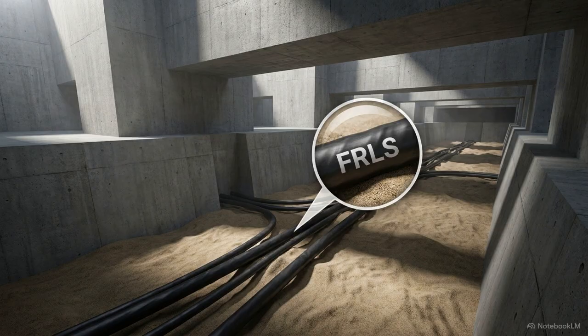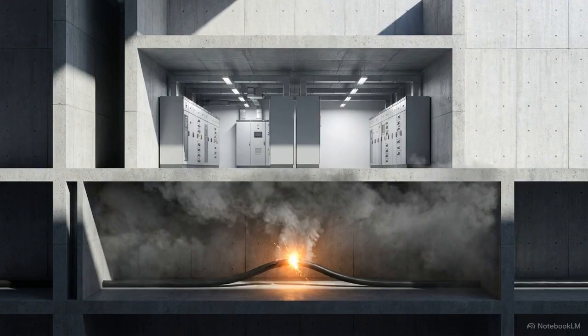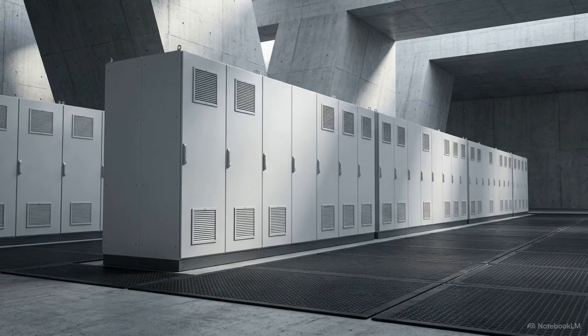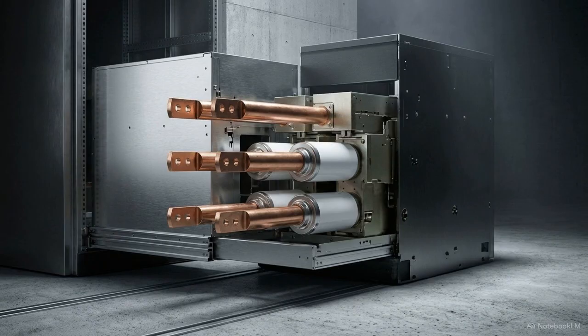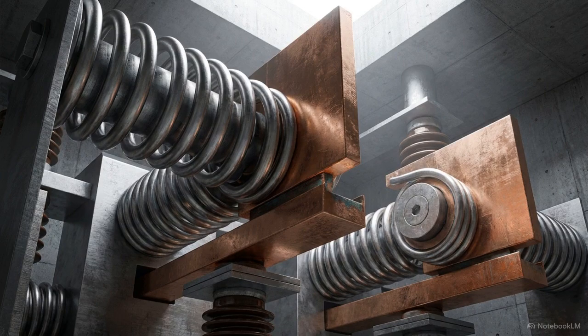Moving from the transformer yard into the underground cable trenches, the power is carried by XLPE cables wrapped in a fire-retardant low-smoke sheath. In enclosed concrete trenches, this FRLS layer ensures a localized cable fault won't fill the vital switchgear rooms above with toxic, blinding smoke. Once the power reaches the main indoor switchgear room, it interfaces with a row of withdrawable vacuum circuit breakers. Vacuum circuit breakers, rather than SF6 gas breakers, are deployed here because they demand zero gas handling maintenance and provide the rapid arc quenching required for the frequent starting and stopping cycles of a pumping station.